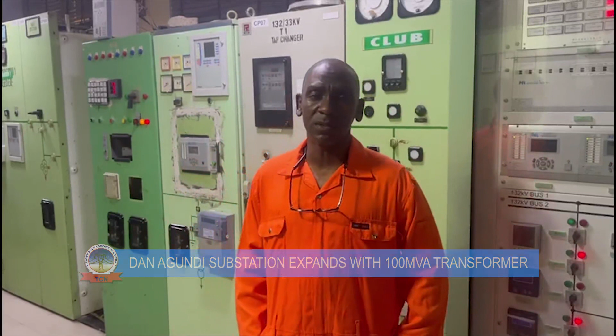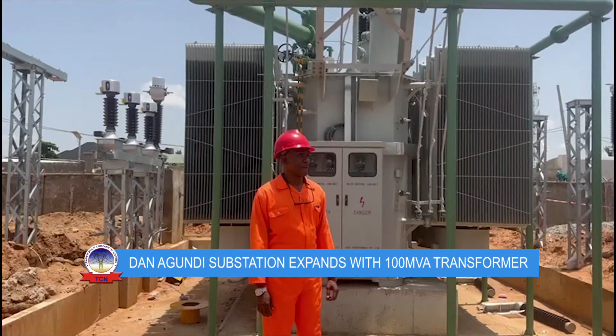The capacity of the station as installed is 180 MVA, that is the installation capacity of 3 by 60 MVA transformers, which means we can transmit up to 144 megawatts at 80%. Recently TCN installed a 100 MVA power transformer, thereby increasing the capacity of the substation.